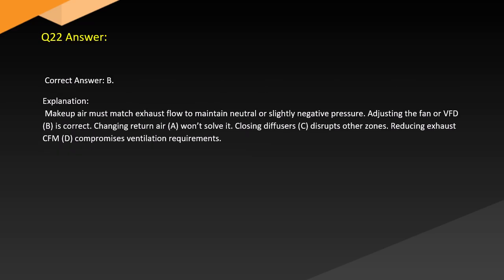Answer. Correct answer: B. Explanation. Makeup air must match exhaust flow to maintain neutral or slightly negative pressure. Adjusting the fan or VFD, B, is correct. Changing return air A won't solve it. Closing diffusers C disrupts other zones. Reducing exhaust CFM D compromises ventilation requirements.